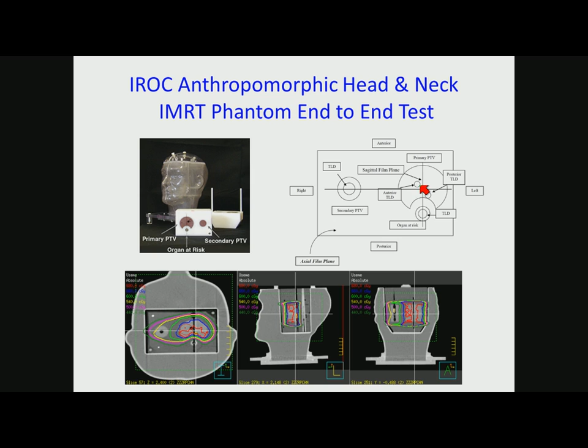And so you plan it. In this phantom, there are some TLDs and some film. They're in different planes, along the axial and along sagittal planes. Once you do this, the therapist scans the phantom, and you send the data to Pinnacle or Eclipse or RayStation or whatever you may have.